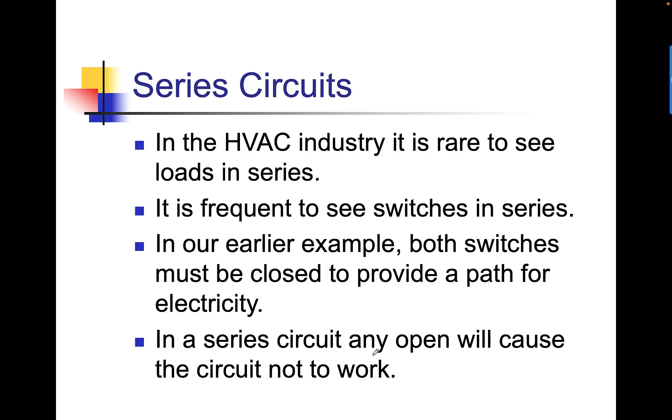In the HVAC industry, it's rare to see loads in series. You don't see it that often. I can think of about four occasions where I've seen loads in series. It's very frequent to see switches in series. For example, safety switches are always put in series because you want all the safety switches to be closed for the circuit to work. It's frequent in our earlier example. Both switches must be closed to provide a path for electricity. I use that example because that's a common scenario. We have safety switches. They all must be closed for the circuit to work.